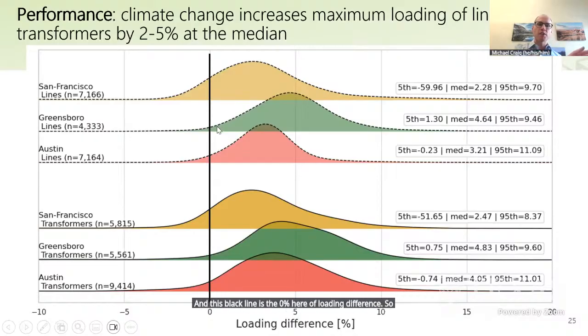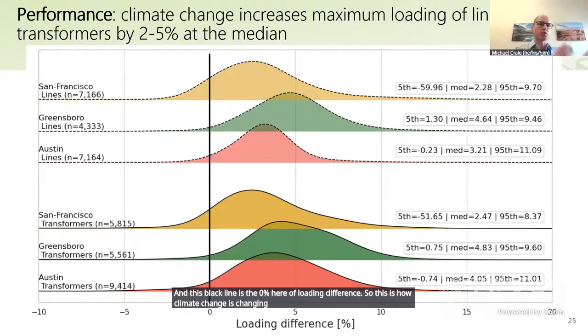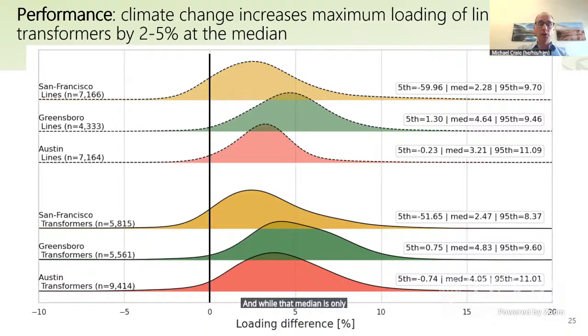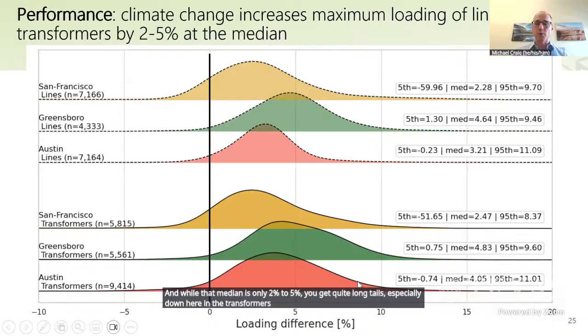This shows how climate change is changing loading, comparing historic to future. We see loading increasing by about 2 to 5% at the median of these distributions—places like Austin are at the higher end, San Francisco at the lower end. While the median is only 2 to 5%, there are quite long tails, especially in the transformers, where 95th percentile values are 8 to 11%. So pretty large increases in loading in transformers, and in some lines as well.